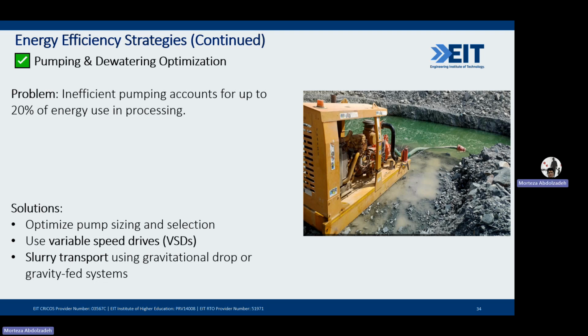Solutions here are optimizing pump sizing and selection, ensuring that pumps are not oversized, which often leads to unnecessary energy consumption. Using variable speed drives allows pumps to adjust their speed based on demand, reducing energy waste during low demand periods. Finally, a slurry transport system can leverage gravity-fed or gravitational drop design to reduce reliance on pumps altogether, further cutting energy use.